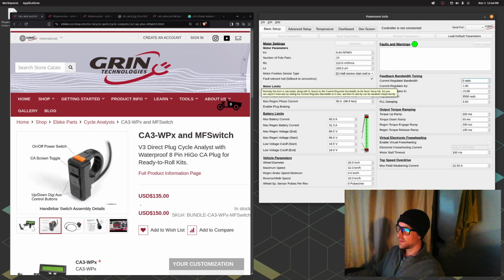If you hover over the current regulator KP label, it says normally this term is calculated along with KI based on the current regulator bandwidth on the basic setup tab -- that's this right here. Usually you just adjust this current regulator bandwidth, and that adjusts the KP and the KI together in some way. So it's a simpler way to adjust this feedback bandwidth tuning, just change the current regulator bandwidth, and you don't have to mess with the KP and KI -- those fields are grayed out and disabled right now.